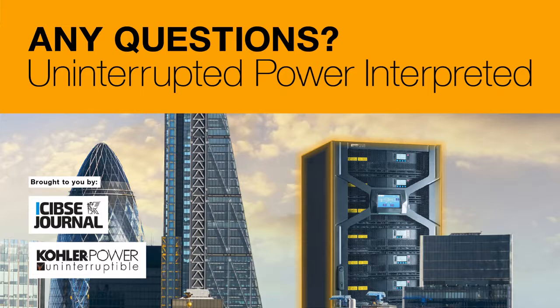Okay, I've got a query here from Jubin, and Jubin asks, is the preferred measure using an input transformer or an output transformer? What is the preference for best performance? I'm guessing this customer is talking about galvanic isolation transformers, which is a transformer used to create a new source, a new neutral reference. And is it best to be on the input or output? It can be either. It depends on the situation. It can depend on the type of UPS, if it's dual or single input. So that is actually the best kind of question to ask directly at the sales point and discuss with your supplier, because it depends on different situations. Okay, thank you for that.